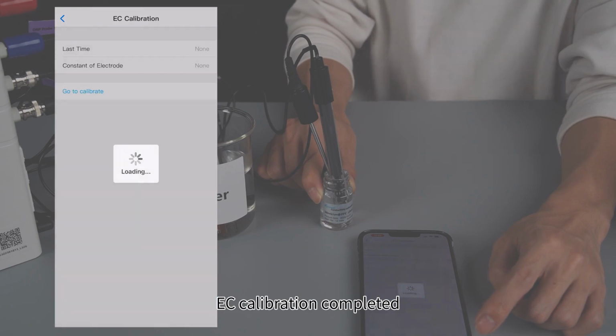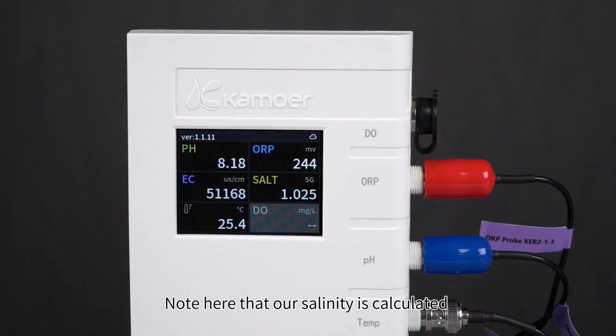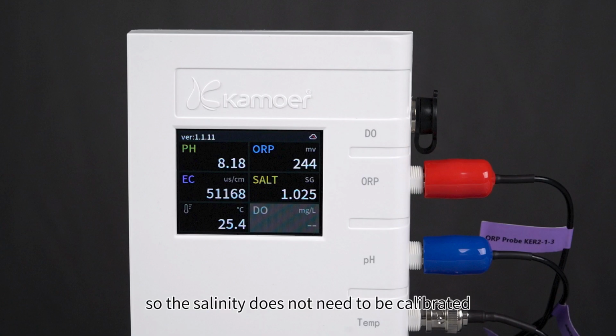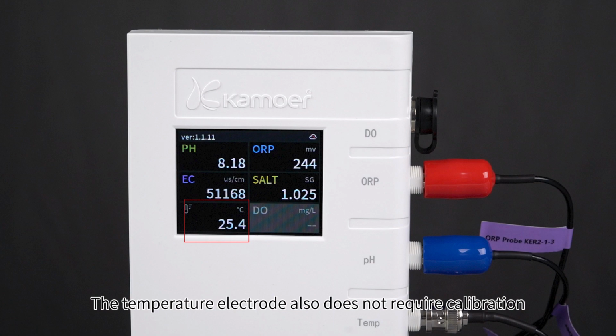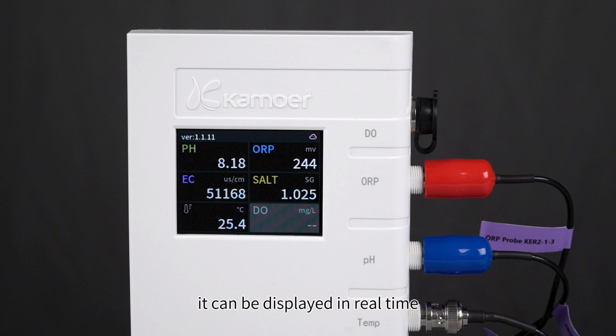EC calibration completed. Note here that our salinity is calculated based on the value of the EC electrode, so the salinity does not need to be calibrated. The temperature electrode also does not require calibration. It can be displayed in real time.